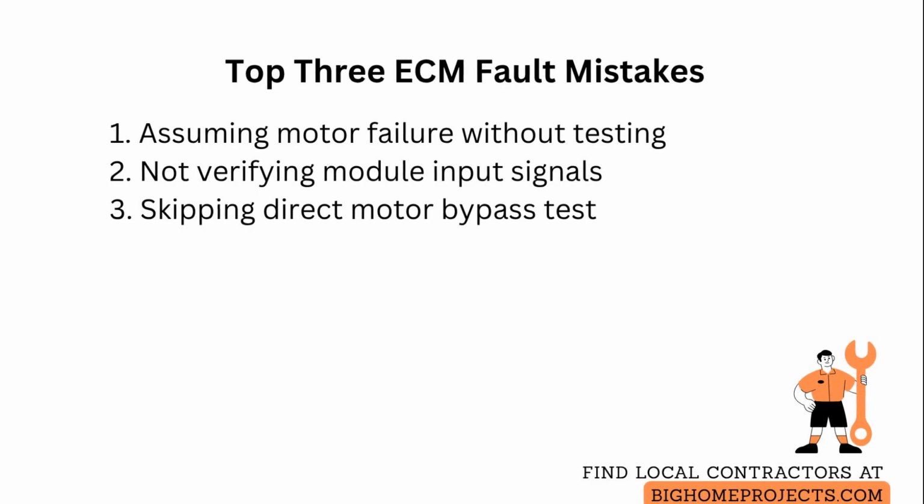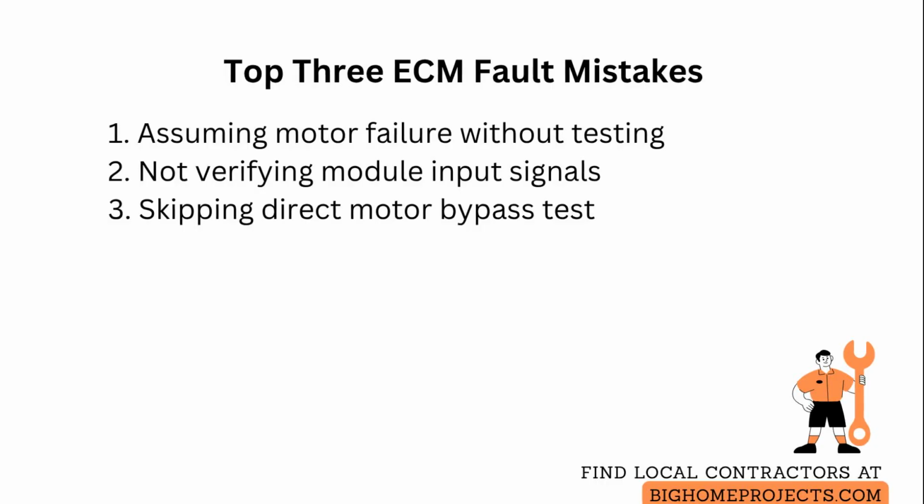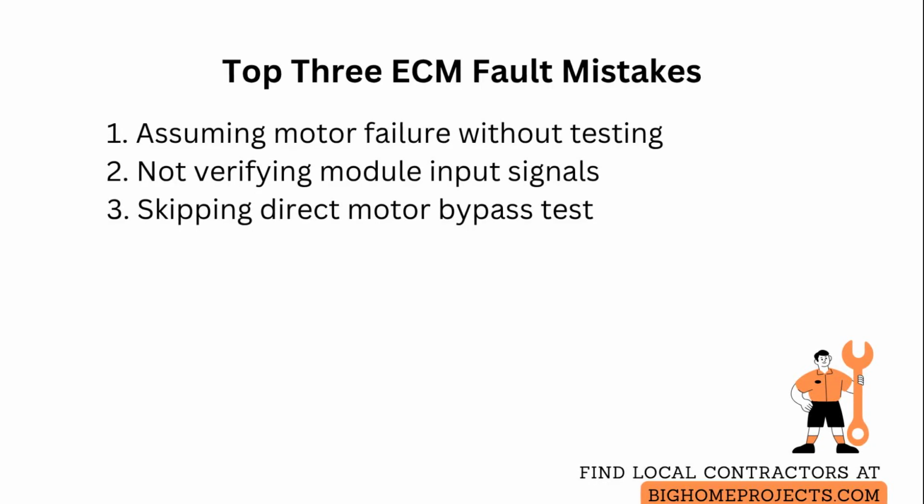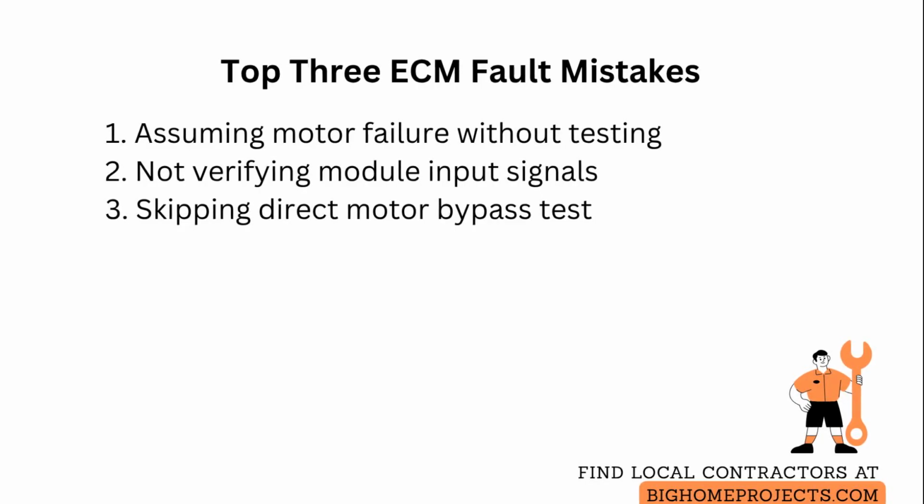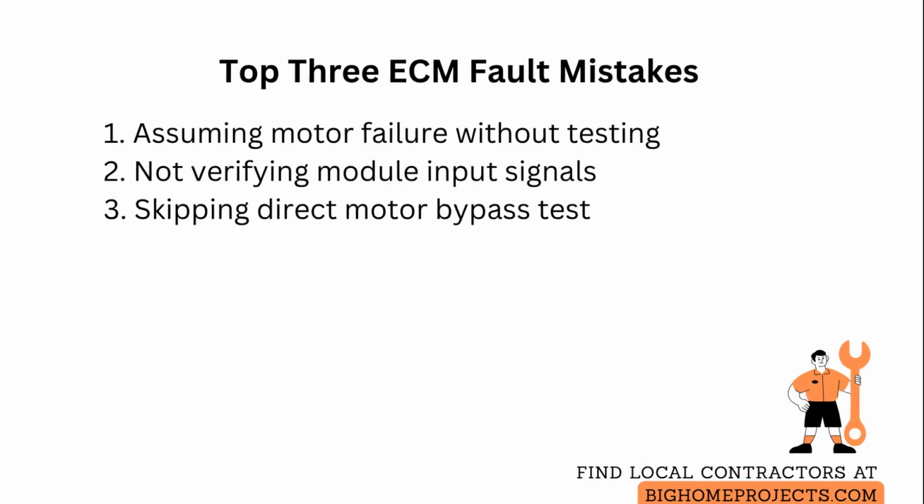Another issue is not verifying correct input power and control signals to the module, causing technicians to replace the module when a control board or blown fuse is the real problem. Remedy this by tracing and measuring incoming voltages and verifying system call signals prior to replacing the module.